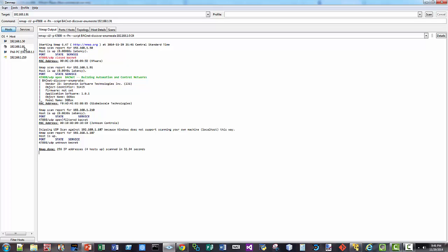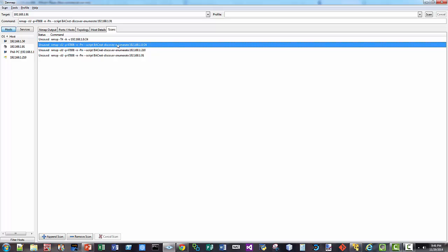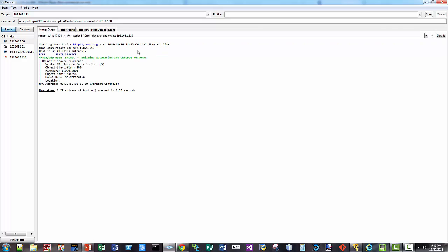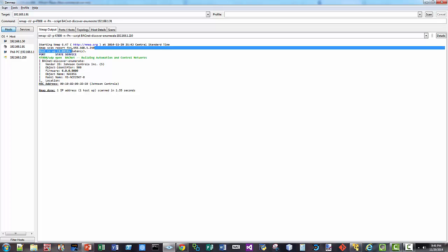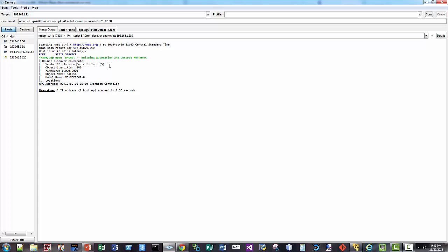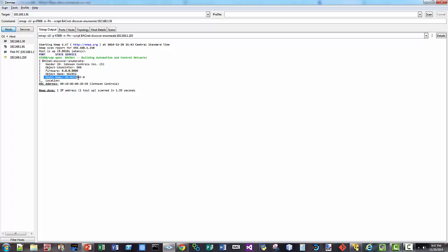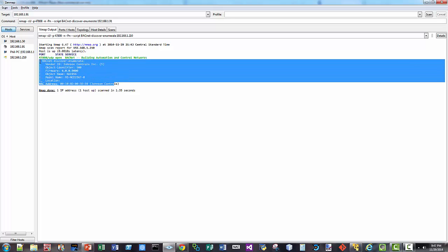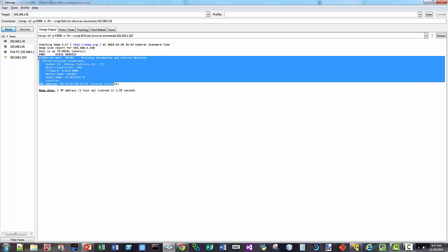So when you're going to do that, I do my scan. I pull that. I pull right here. I pull the 210 address is my next scan. So I enumerate this. I find my Johnson Controls. And it tells me the BACnet object identifier. So if I wanted to attempt to connect to this BACnet IP device and pull its points or do something like that, I could do that. If I wanted to look up any vulnerabilities with this firmware, I could do that. I find the object name. I find the model name. And I've got the MAC address. So right off the bat, I've done some pretty good enumeration to find out some information about these BACnet devices that are on that network.